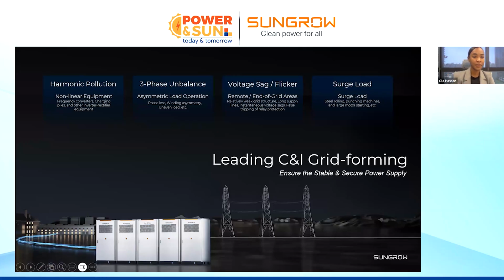So the advantages of this kind of systems is, first of all, it's suitable for non-linear equipment and unbalanced three-phase loads, because this kind of system can provide unbalanced output on the phases as well. So if one of the phases is like 30 kilowatt, another one is 25, and another one is 10, the system is very smart. It will adjust its output according to the unbalanced three-phase loads. Also the voltage flickering. So in case of weak grid structures, we are able to support this kind of applications, and also loads with high surge current or high inductive starting currents as well can be supported with the C&I BESS system. So it's C&I grid forming.